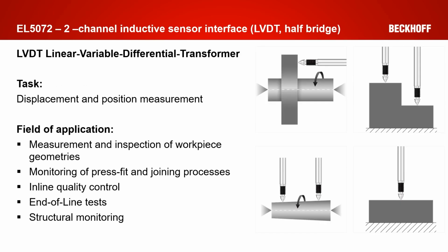LVDT means linear variable differential transformer. So it's a transformer with some special design to be used for displacement, length, or position measurement tasks. LVDTs are passive devices, so they don't have any electronics included, and therefore they are often valued for their lack of electronics, which makes them not sensitive to external influences. Furthermore, the measuring range is often only a few millimeters with a high accuracy in the micrometer range. The advantages are obvious. It's a very precise and cheap solution with no mechanical wear. Therefore, there's also a wide field of application for this kind of sensor.